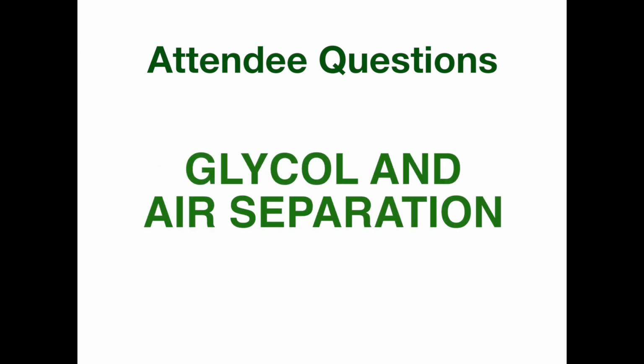And another question, there are some questions on glycol again, concerning glycol and air separation. Yes, anytime you put glycol in a system, it's going to lower the efficiency of removing air out of the system. The reason for that is glycol has a higher boiling temperature than water. Glycol will boil at, I guess, 380, and water, what, 212 at atmosphere.